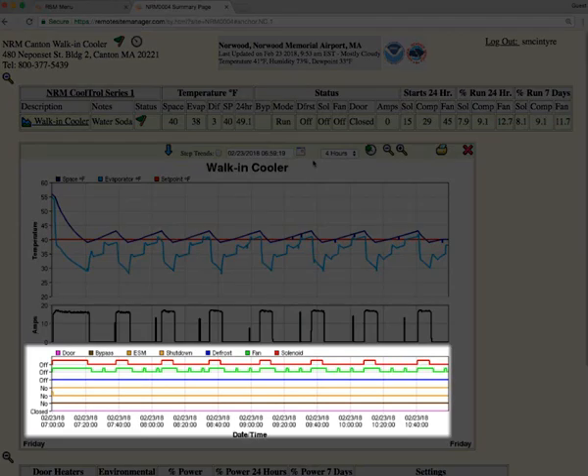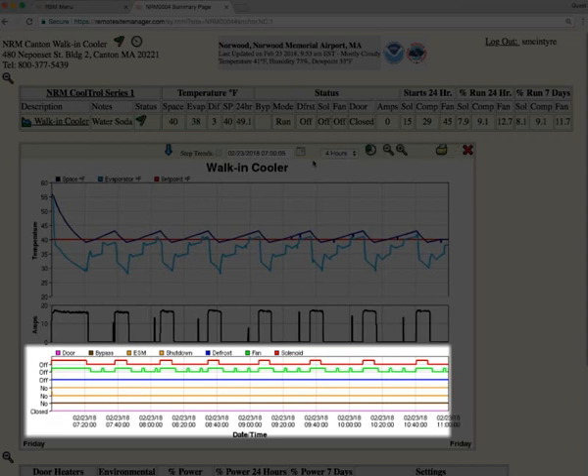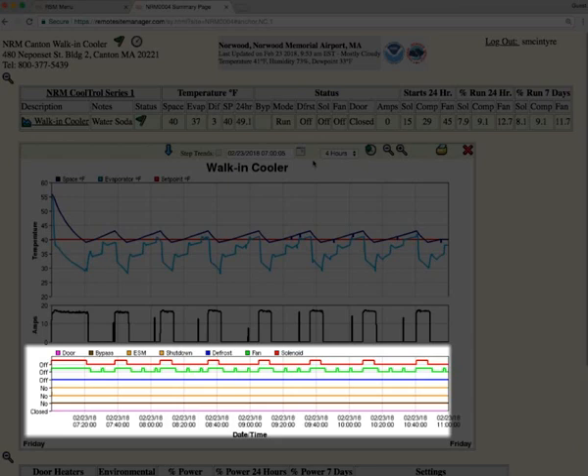This section is the amperage of the compressor. And then this section down here is the trace of what our controller is doing. Every time you see a line in the up position, that means it's calling for that item. Then we have the shutdown line. We have the ESM, which stands for energy savings mode, which is a setback scenario on a walk-in cooler. Then we have the bypass. And then the bottom line is the manned door being opened or closed.